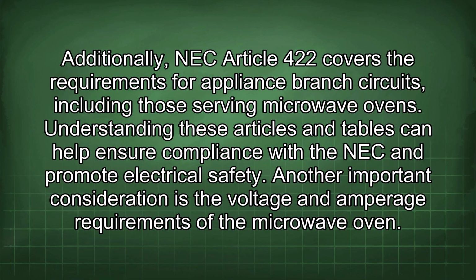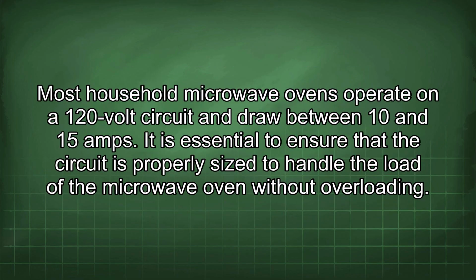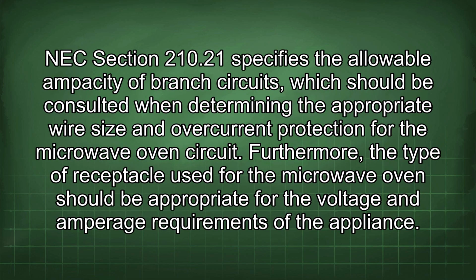Another important consideration is the voltage and amperage requirements of the microwave oven. Most household microwave ovens operate on a 120-volt circuit and draw between 10 and 15 amps. It is essential to ensure that the circuit is properly sized to handle the load of the microwave oven without overloading. NEC Section 210.21 specifies the allowable ampacity of branch circuits, which should be consulted when determining the appropriate wire size and overcurrent protection for the microwave oven circuit.